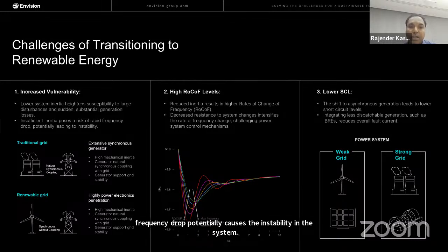The reduced inertia also results in a higher rate of change of frequency, or RoCoF, because the decreased system resistance intensifies the rate of frequency change. So how can the grid respond to this? One element is securing against the largest loss. Maybe we need to add, or the grid has to get, some support like 1 or 2 gigawatts from external support, maybe ancillary services, or maintain the RoCoF within 0.5 hertz per second.